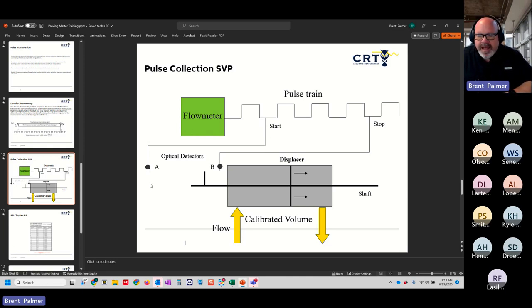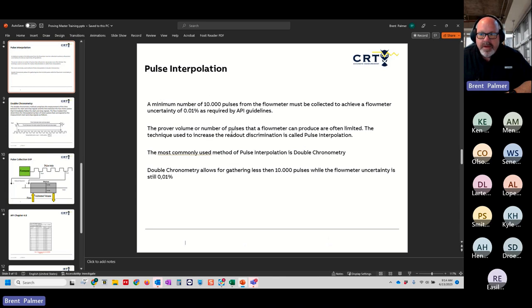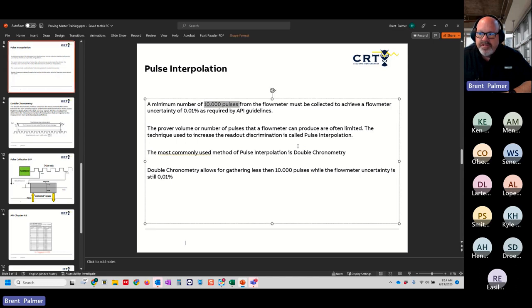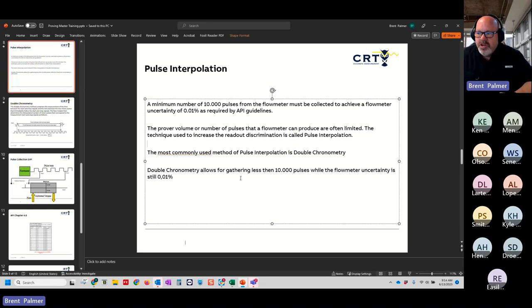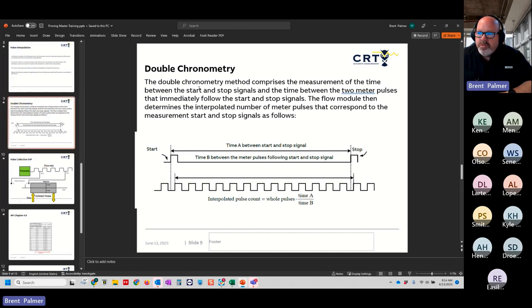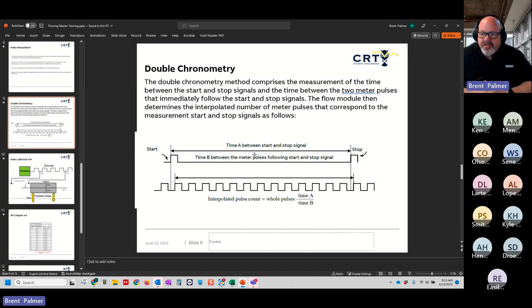Pulse interpolation is a way to handle situations where we can't get 10,000 pulses from the flow meter — which would give us an uncertainty of 0.01% in the prover volume — so we turn on pulse interpolation. The most common method is double chronometry, which allows gathering fewer than 10,000 pulses while the flow meter uncertainty is still at 0.01%. Double chronometry measures the time between the start and stop signals and the time between the two meter pulses that immediately follow the start and stop signals, producing a pulse-interpolated time that's applied to yield a total interpolated pulse count equivalent to 10,000 pulses.